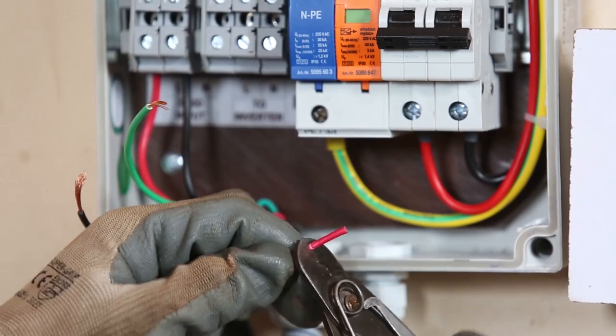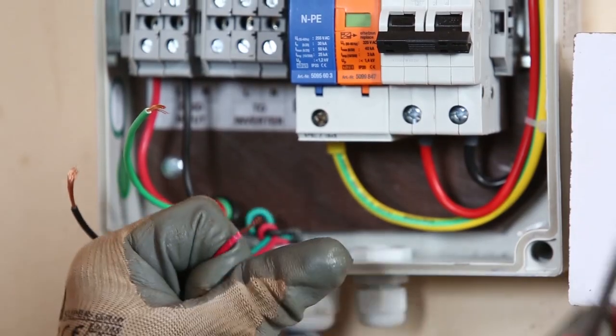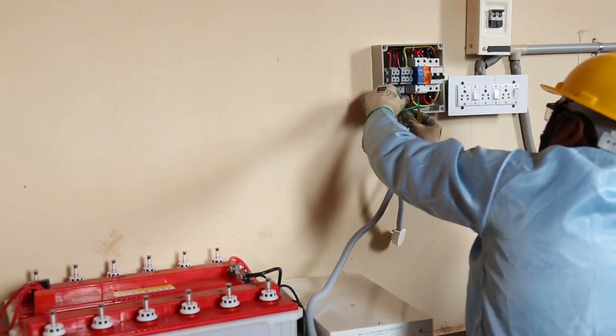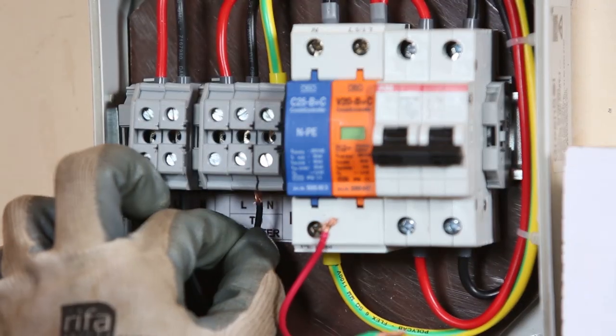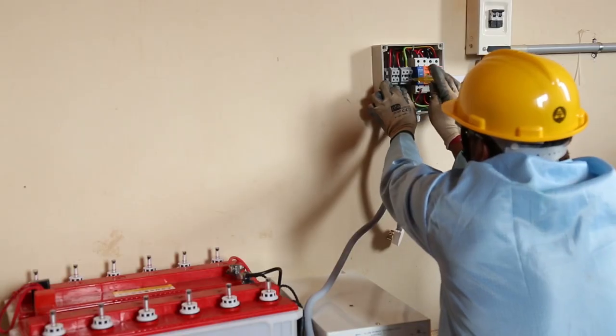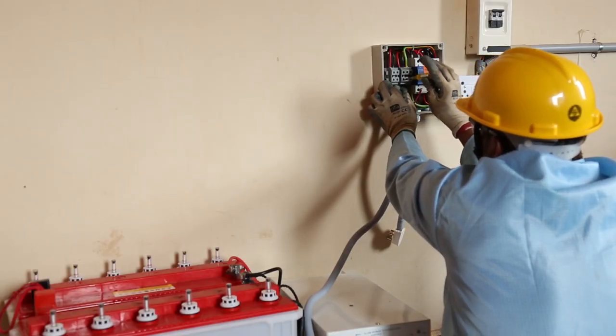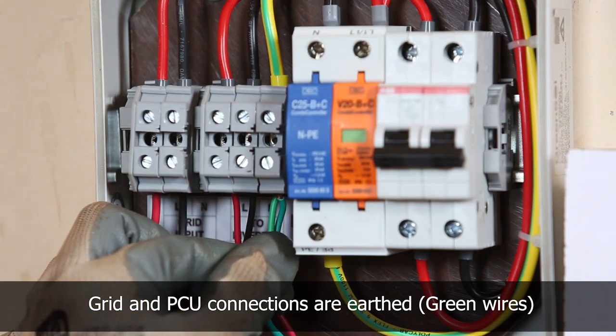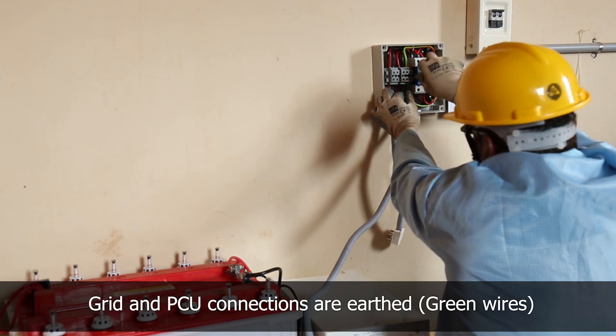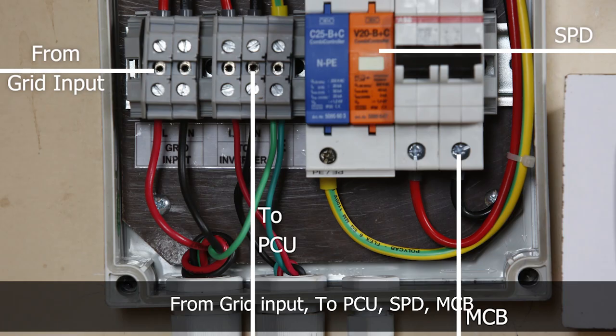Strip the next set of red and black wires and connect them to the output terminal of grid protection box. Connect the earthing wires of the grid and power conditioning unit together to the earthing terminal of the grid input protection box. The grid input protection box connection is complete.